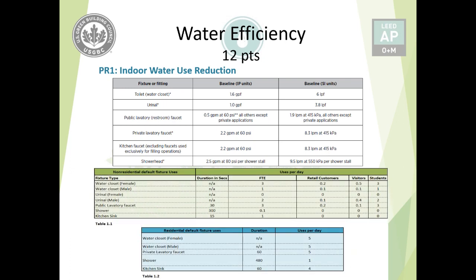You have to know how many people are using the fixtures and for how long. We have different fixture types and different user types. We have FTEs — full-time equivalents — people who are spending more than 8 hours a day in the same facility. Retail customers are a certain percentage of FTEs, visitors also a certain percentage, and students are equal to FTEs. This applies for commercial units, and there is a similar concept for residential units.